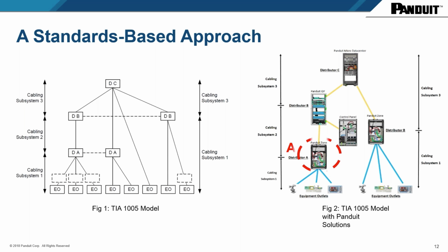And as you start looking at each one of these points, you will find that at distribution A, this is where connectivity is probably at a MICE 3 category, and you have to worry about that environment. When you go to a B, you will encounter more of a MICE 2, and you go up to C and you find a MICE 1 category, where you really shouldn't worry about that environment.